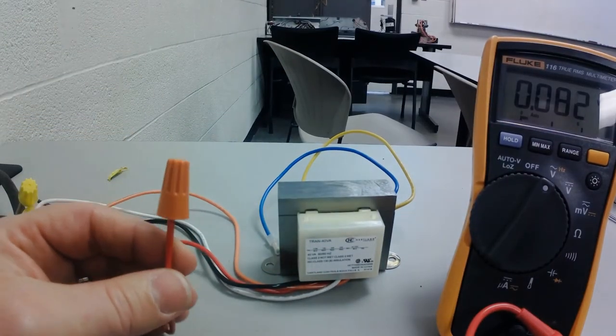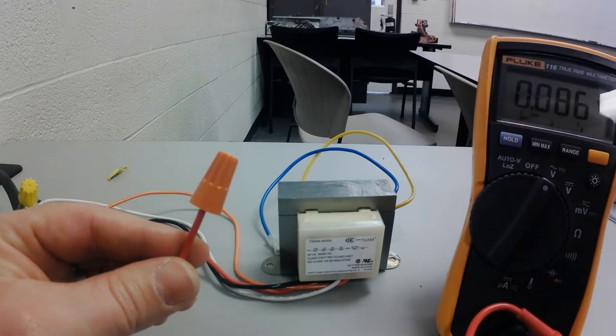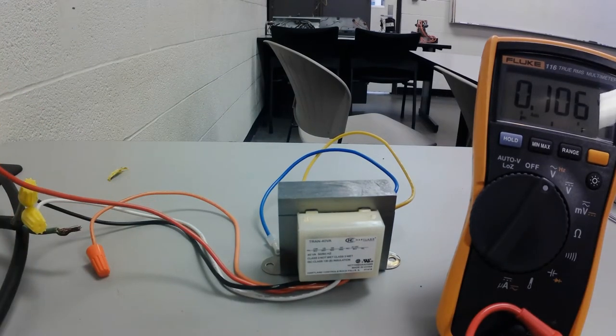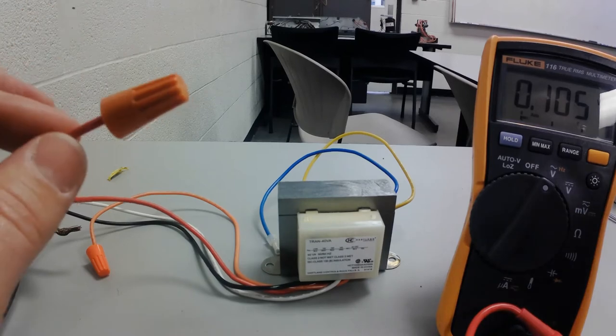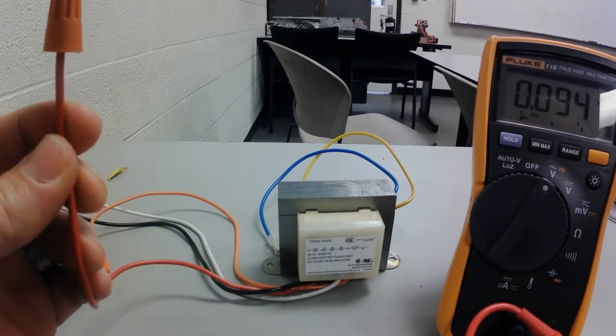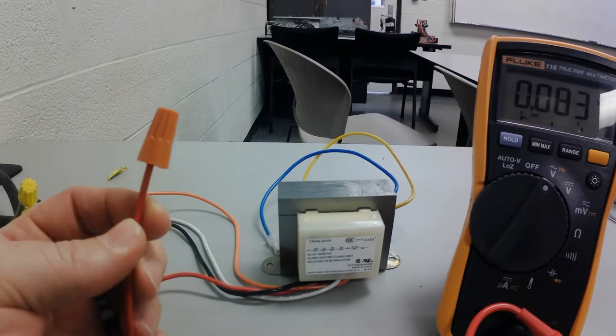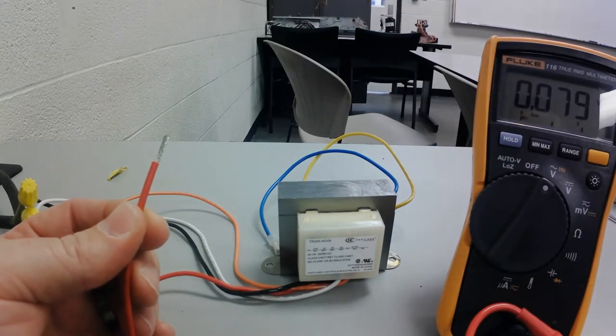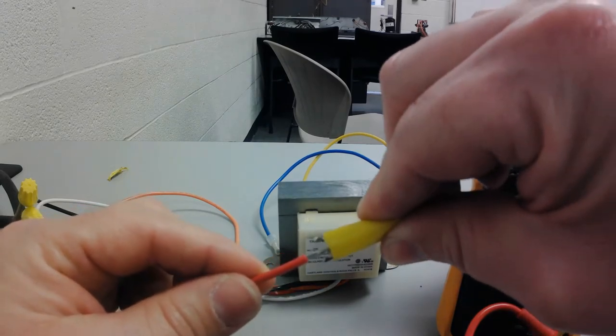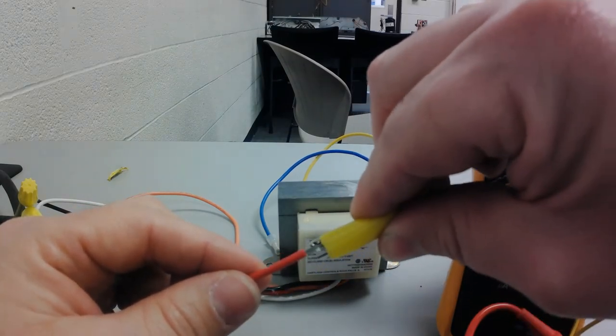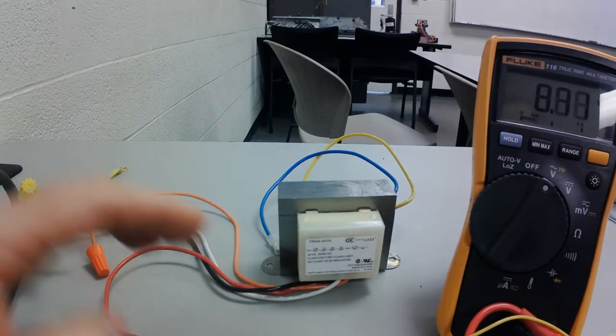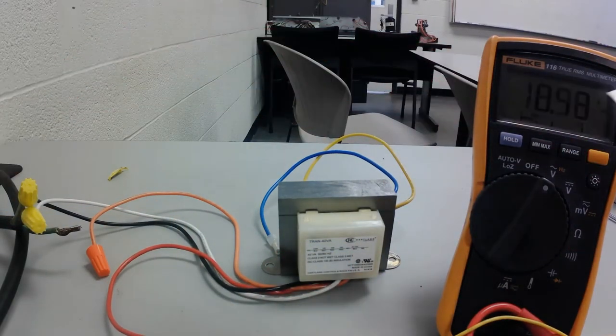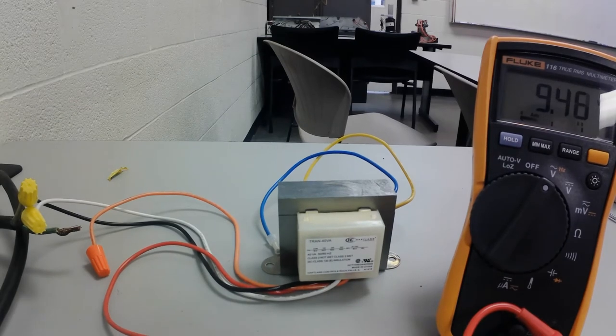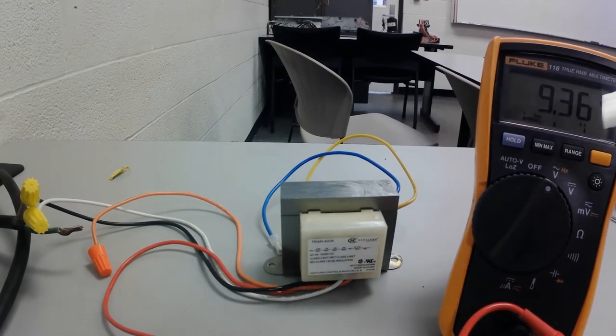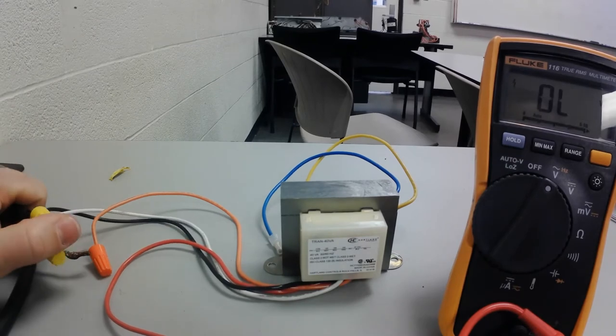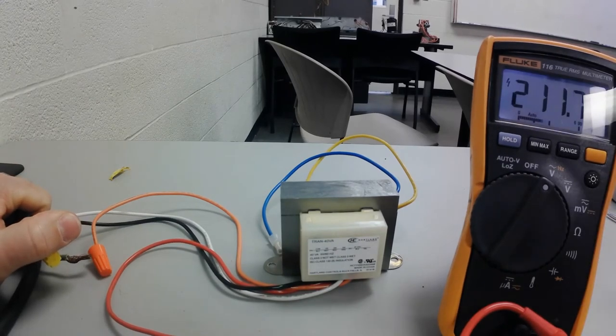So let's just say that I want to check the red wire, even though it's not being used right now, I'm running 120 volts into the primary side of this winding. But what if I check the red wire right now? If we do that, what you're going to see... that in there. There we go. I'm going to lay that right there. And I'm going to take my other lead, I should say, and I am going to put it into this side. Now look at that.